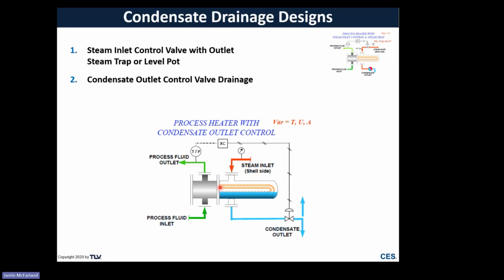Because this is designed to back up water, we've got a degradation of U, we've got a varying A, so it becomes a very sluggish type response. And over time, as this slowly degrades the heat transfer coefficient, it's going to lower the amount of temperature that can be provided to the process, which will then feed back to our controls and say, hey, control valve, you need to open up more. So that liquid level will drop and drop and drop till eventually there's no liquid level inside the process heater, and it could be past the point of return, in a way saying that there's no more liquid level to be drained. And so what's to stop this control valve from just blowing live steam? That's a big problem that we see. Keep a lookout for that.